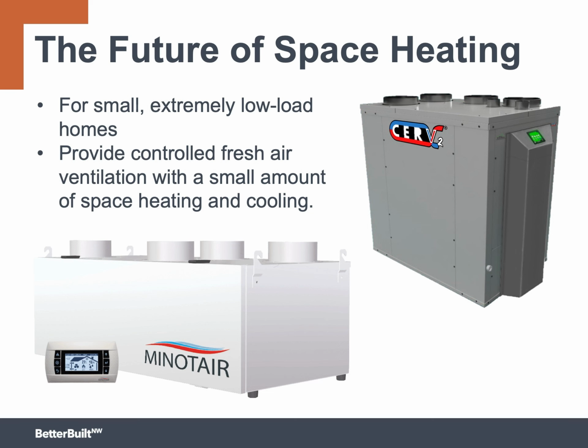Small, super high-performance homes, such as those built to Passive House or Zero Energy standards, should consider a highly efficient heat recovery ventilation system. These two units use heat pumps to recover heat and have a small amount of space heating and cooling capacity. If the building loads are small enough and the climate is mild enough, one of these might be all you need.